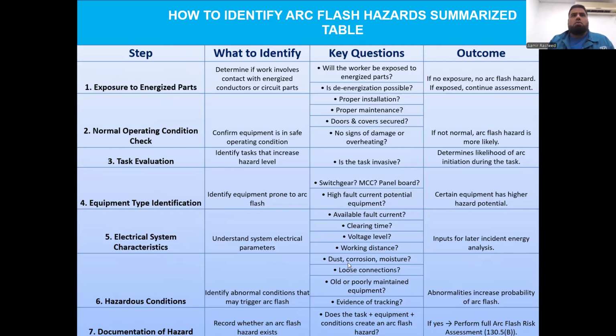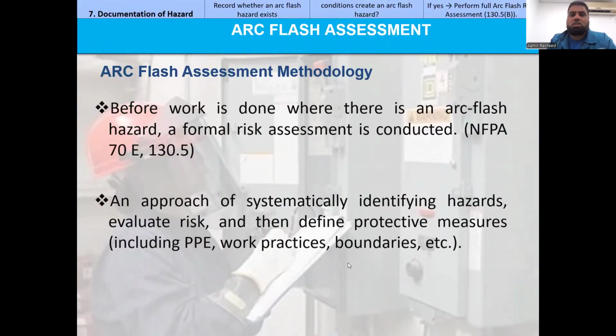And then we talk about the electrical system characteristics, like electrical parameters: the available fault current, clearing time, voltage level, working distance, and hazardous conditions, any abnormal condition that may trigger an arc flash, such as dust, corrosion, or loose connection. Then documentation of these hazards: record whether an arc flash hazard exists. Is this task, equipment or condition creating any hazard? If yes, then you should move ahead towards the arc flash risk assessment.